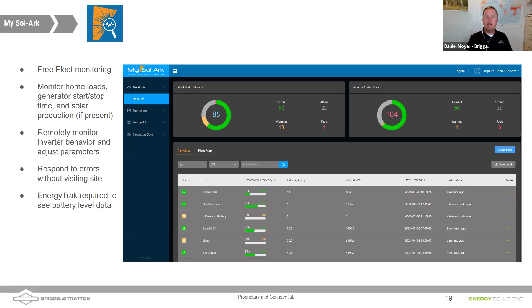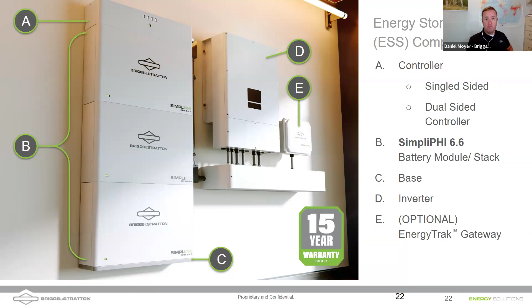Every system does need that controller up top. You can have up to 3 batteries, the SimpliPHI 6.6 kilowatt hours each. Stack them together and you get 20 kilowatt hours. We have a base at the bottom, either floor or wall mounted, universal. The letter D is going to be your Sol-Ark inverter. We also have an optional EnergyTrak app, which allows us to get more granular detail on the batteries, and it also allows tech support to push firmware updates. It's optional. There's a 15-year warranty on our batteries, unlimited cycles, 100% depth of discharge, with no throughput as well.